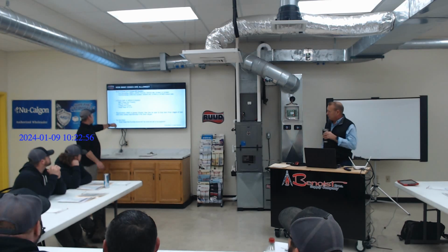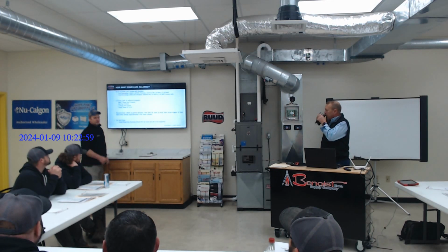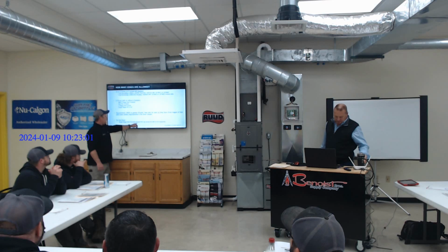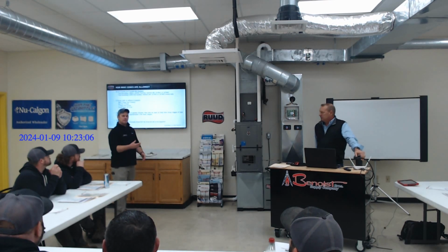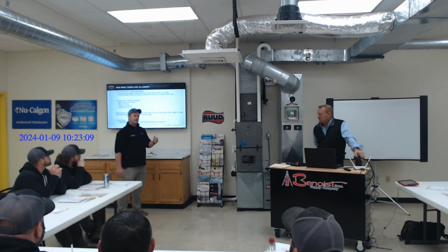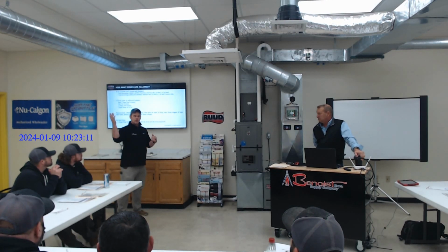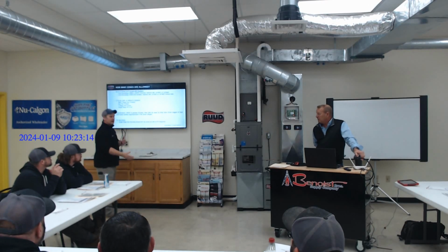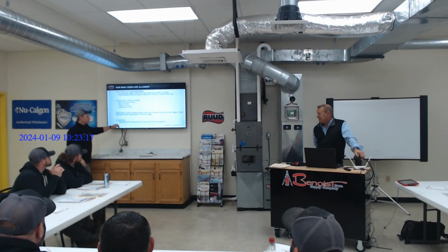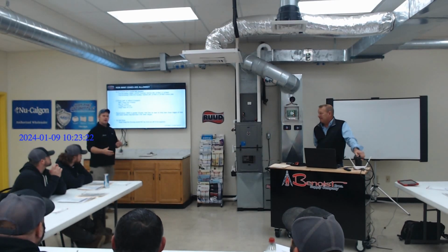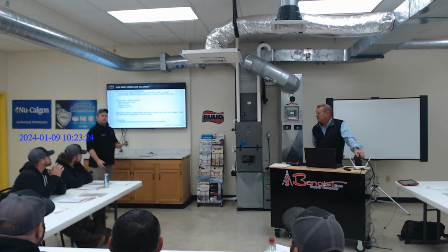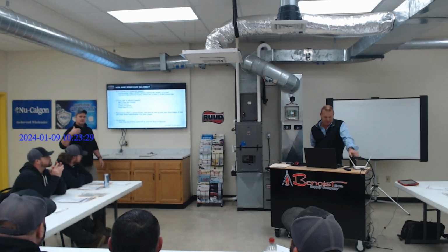I just want to emphasize one point. Guys, if you look down here to the bottom, do not zone single-stage gas furnaces and air handlers. Not to be zoned and will not be supported. That's important. Why? Because of what he talked about in the beginning. We need that stage independent on that smallest zone, right? So I want to reiterate that, even though he went through that, that's important. I know we've done it in the past with Honeywell boards and things like that, but that's why we're trying to keep you from running into future problems. We need that two-stage furnace so that we can accommodate our smallest zone, right?